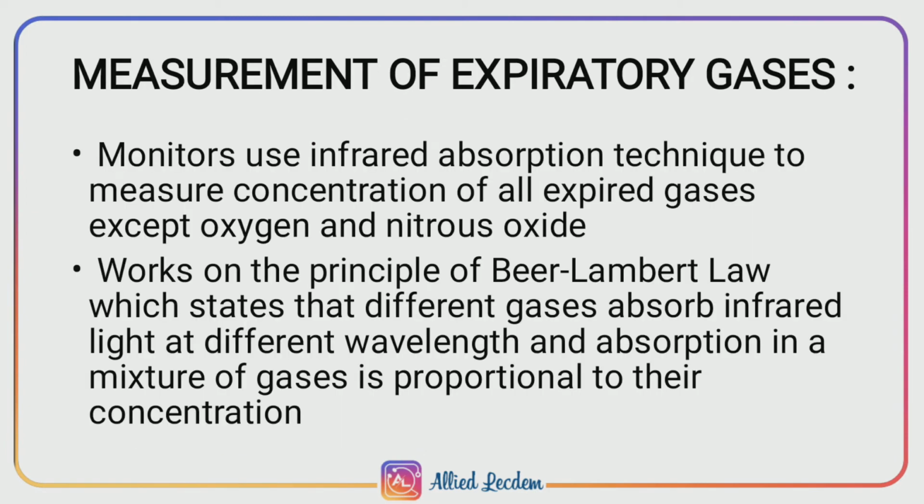Measurement of expiratory gases. Various techniques such as mass spectrometry, Raman gas analysis can be employed to analyze and measure the concentration of expired gases. However, in the current day practice, all monitors use infrared absorption technique to measure concentration of all expired gases except for oxygen and nitrous oxide.